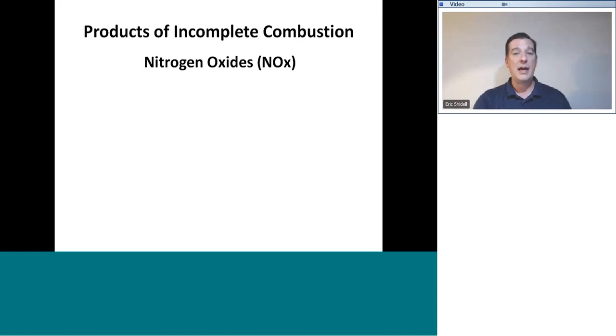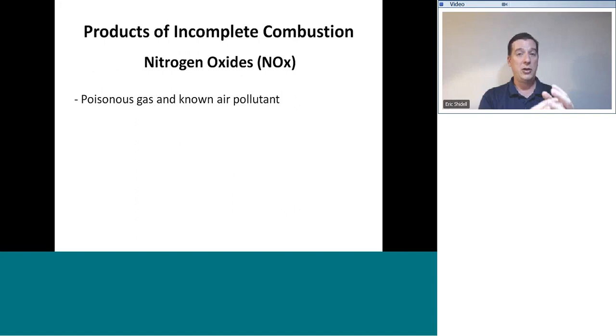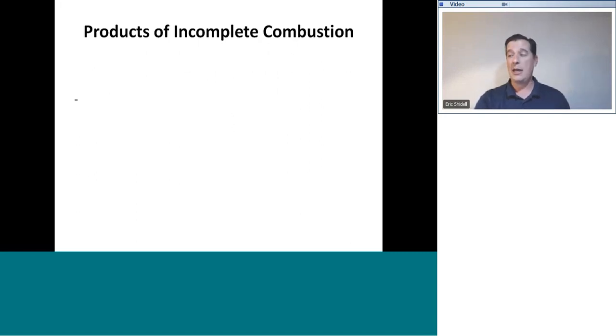Another product is called nitrogen oxides, also known as NOx. You may hear talk about NOx filters or low NOx burners. NOx is essentially a generic term for a family of gases called nitrogen oxides, and there are several of them. Remember, nitrogen is an inert gas, but in an unstable flame, oxygen will combine with nitrogen and create an oxide of nitrogen, and that is a poisonous gas and a known air pollutant. And tuning our burners is going to minimize the production of nitrogen oxides.